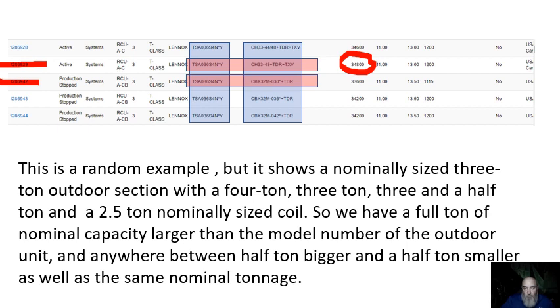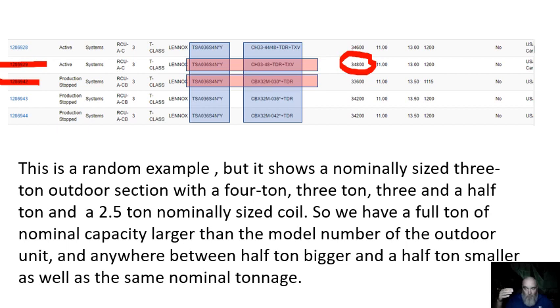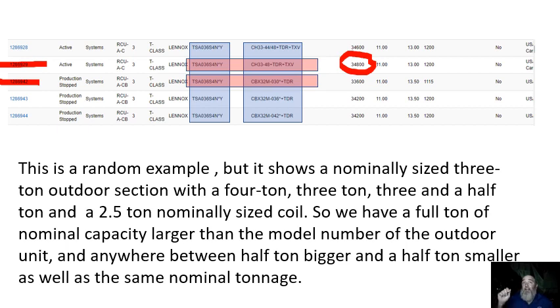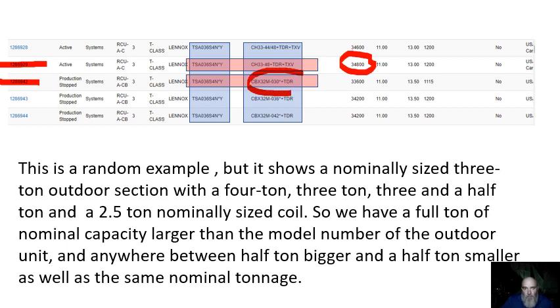In my world, there's no such thing as a 3-ton outdoor unit and a 4-ton coil. There are two pieces of equipment that, when they're put together, produce a capacity somewhere around 3 tons that you can see right there. An 036 with an 048 producing 34,800 BTUs. That's at ARI conditions. But right below here, look at this coil that I just circled. It's an 030, a 2.5-ton nominally sized coil.